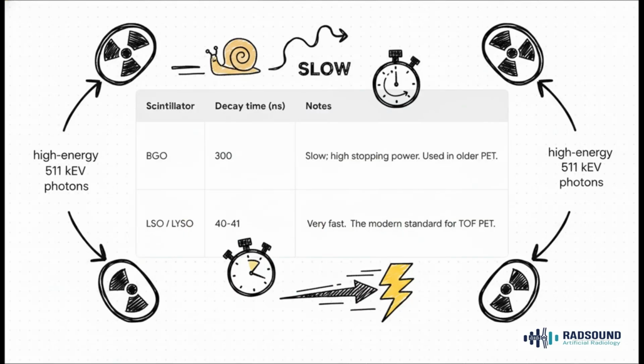Now for PET imaging, we need something totally different. We're detecting those powerful 511 keV photons, and we have to do it incredibly fast. The old school standard was BGO. It's dense, which is great, but man, it is slow. We're talking 300 nanoseconds for that flash of light to fade. The modern standard is LSO or LYSO. And just look at that decay time, 40 nanoseconds. It is ridiculously fast. And that incredible speed is what makes modern time-of-flight PET possible. It's a simple story. Speed wins.